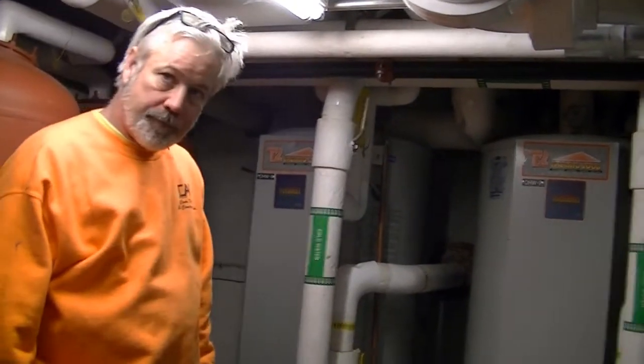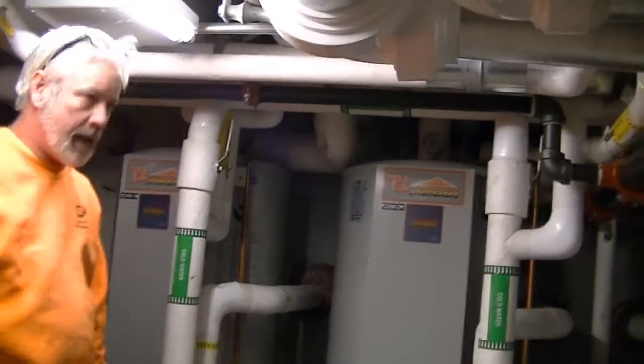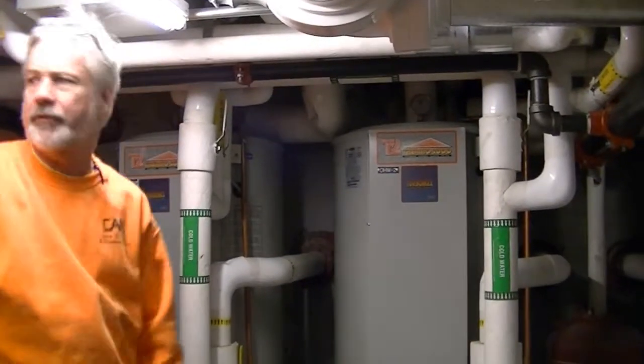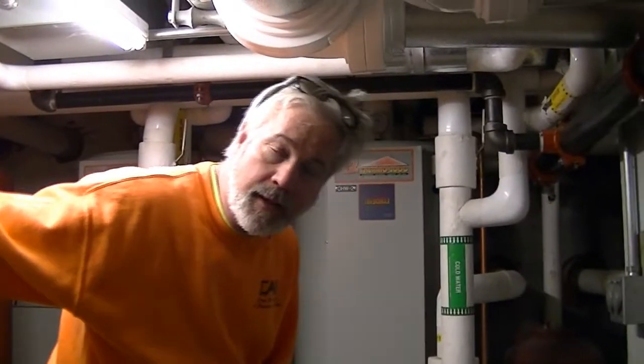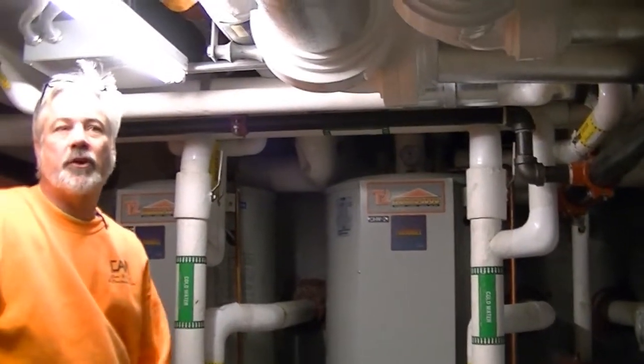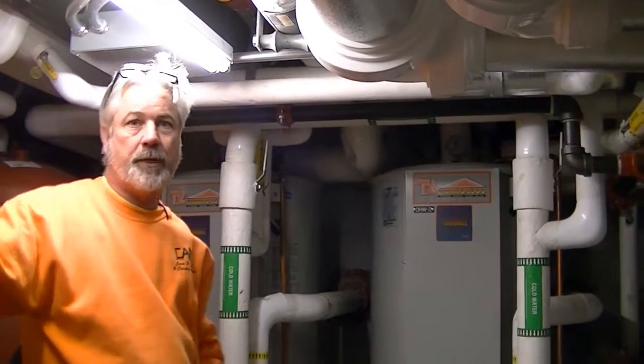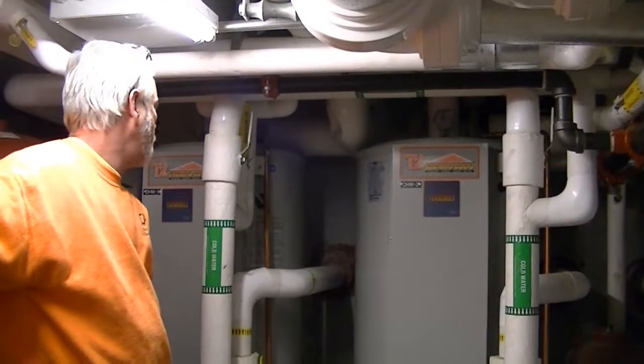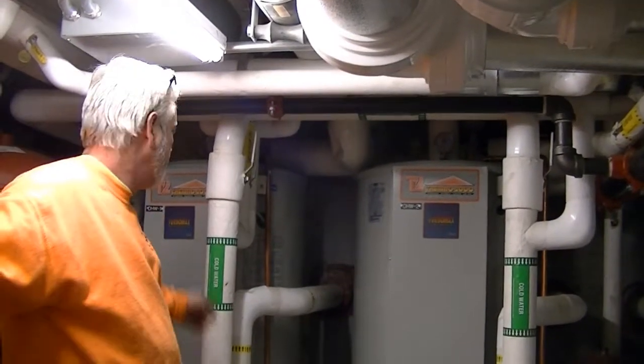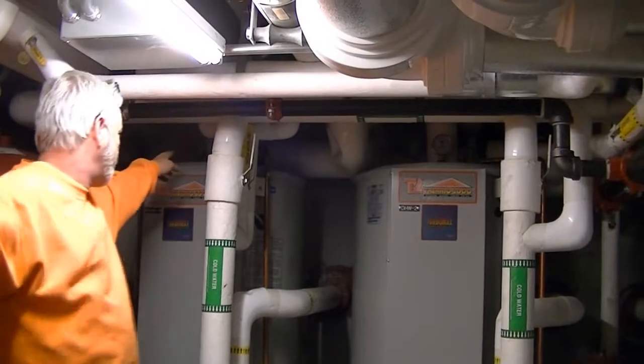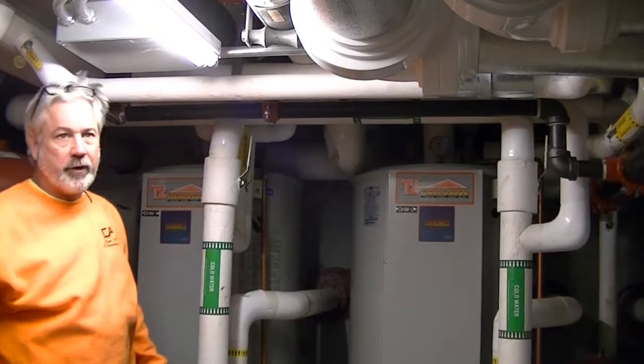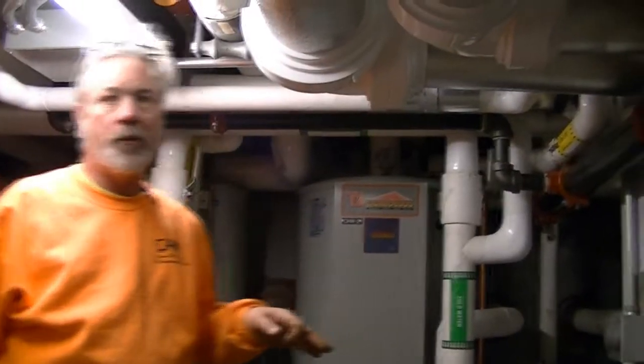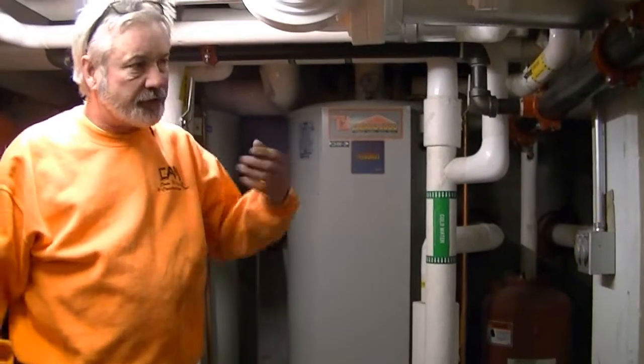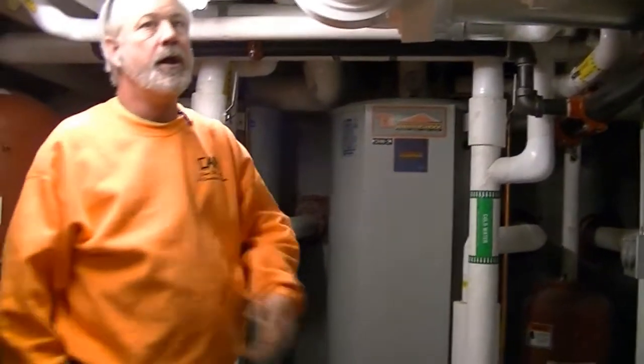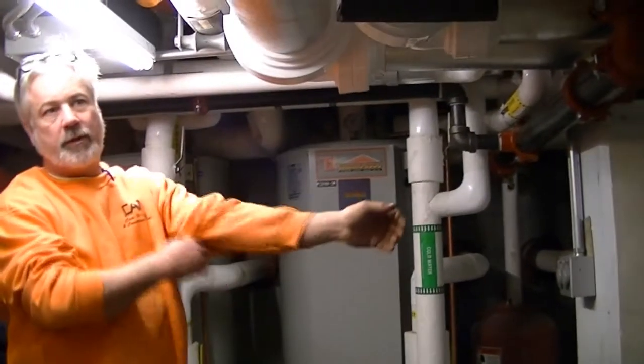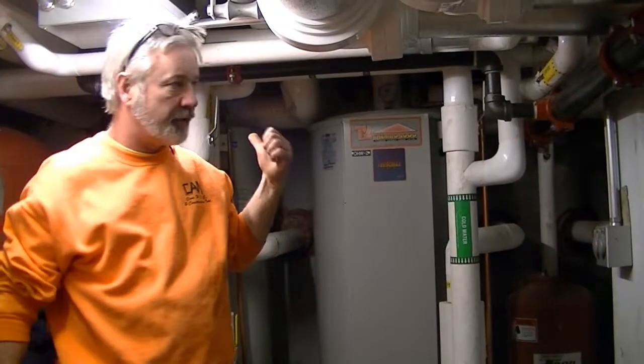If there's a problem with that temperature sensor, would that show up down in the boiler control? Yeah, you would get an error code on that. Is Kevin still here? Kevin? Yeah, if you have a sensor fault, it's going to tell you you've got a sensor fault because the sensor goes back to the Viessmann panel. So when you look at what the domestic hot water temperature is, it'll tell you right here. You can also compare it to what's up here. Okay? In your display screen downstairs, when you log into the set point, you can adjust the set point. If you go to system information and go to domestic hot water, it'll tell you what the tank temperature is. Okay? Instead of what the boiler is set for, it'll tell you what it's actually putting out.